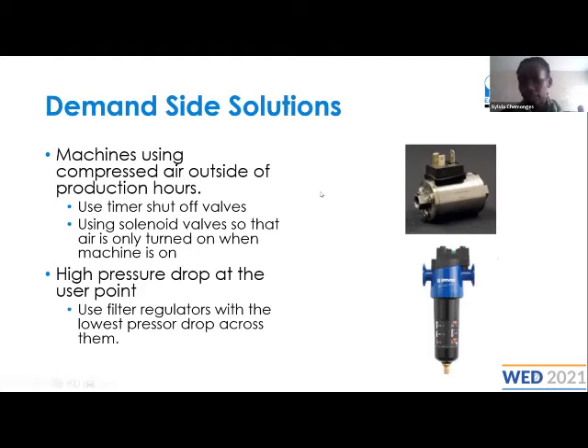Another thing would be for manufacturing sections that do not need compressed air at a particular time, there are valves that can open and close when compressed air is required at the use point. So incorporating any of these two valves, you will be able to save almost 50% of the total compressed air that you require within that section.